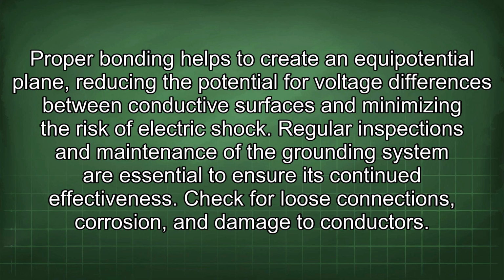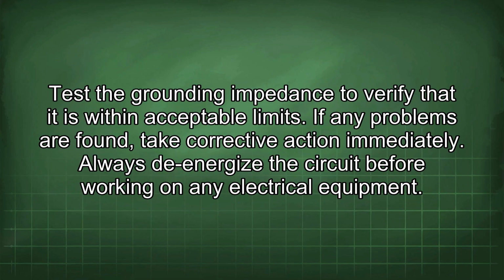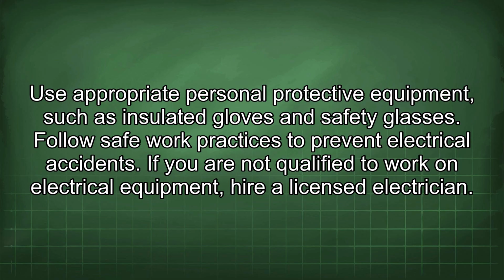Check for loose connections, corrosion, and damage to conductors. Test the grounding impedance to verify that it is within acceptable limits. If any problems are found, take corrective action immediately. Always de-energize the circuit before working on any electrical equipment. Use appropriate personal protective equipment, such as insulated gloves and safety glasses.